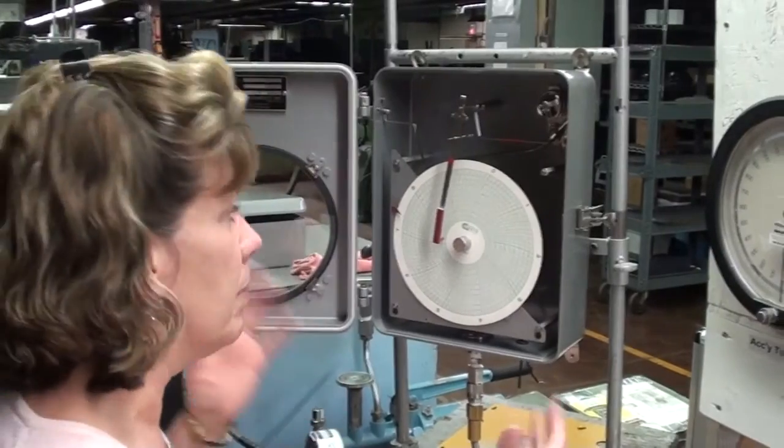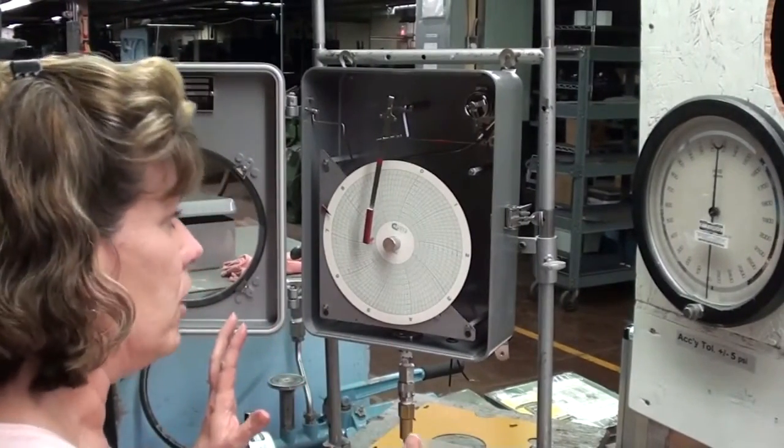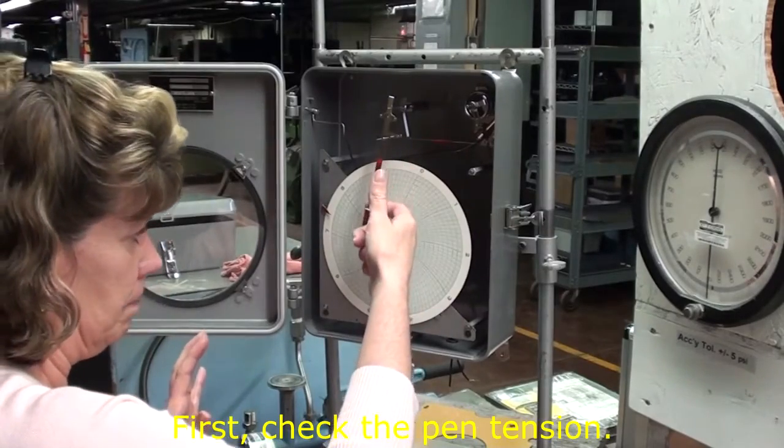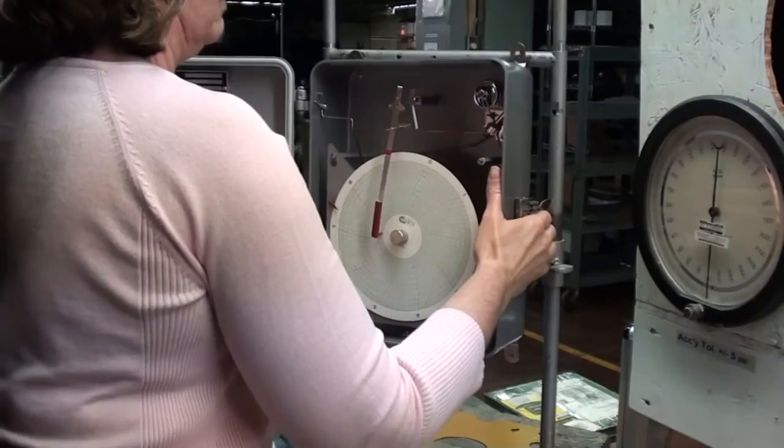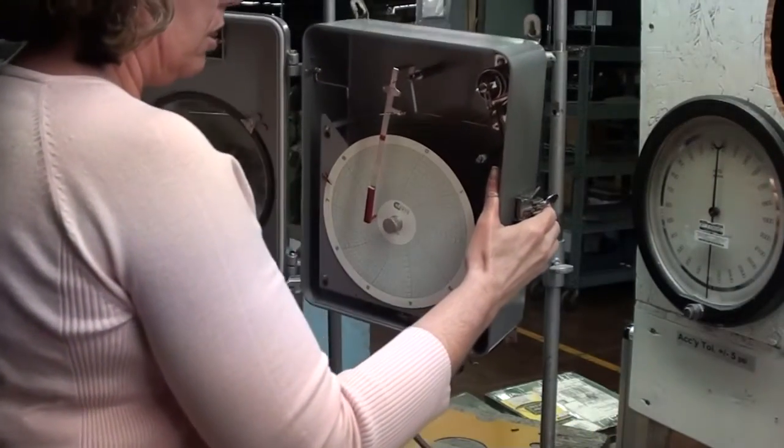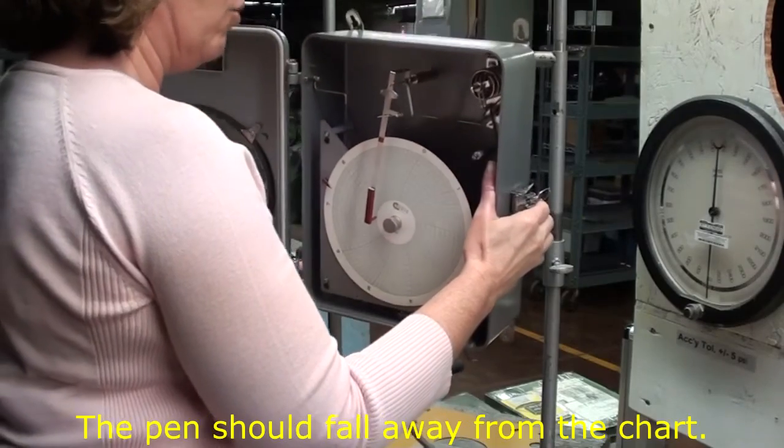The first thing that you want to do in calibrating a pressure recorder, or any recorder for that matter, is check your pen tension. You should tilt the recorder about this much and the pen should fall away from the chart.